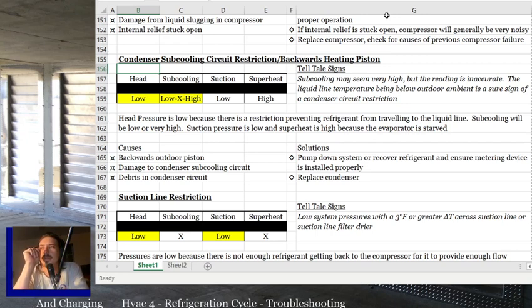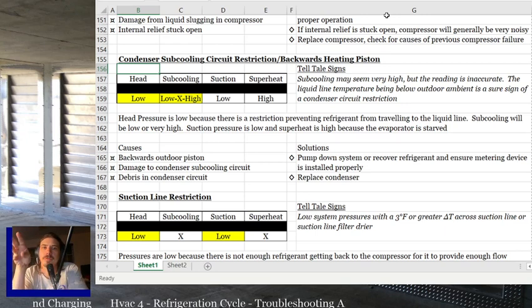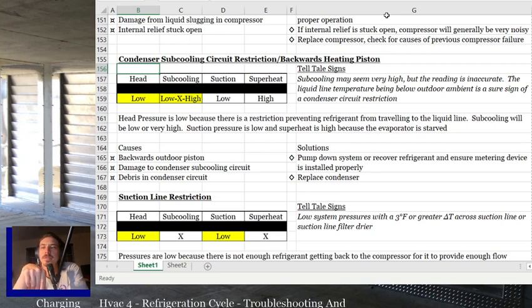condenser. If you don't know, the last circuit in a condenser, the very bottom circuit, all the refrigerant goes through. All the refrigerant gets distributed to multiple lines inside the condenser, and then they come back together. Then they go down, and they all together go through the last loop of the coil, basically, and that's the subcooling circuit. So that's the very last spot before you exit the condenser. It's the very last part of the circuit.